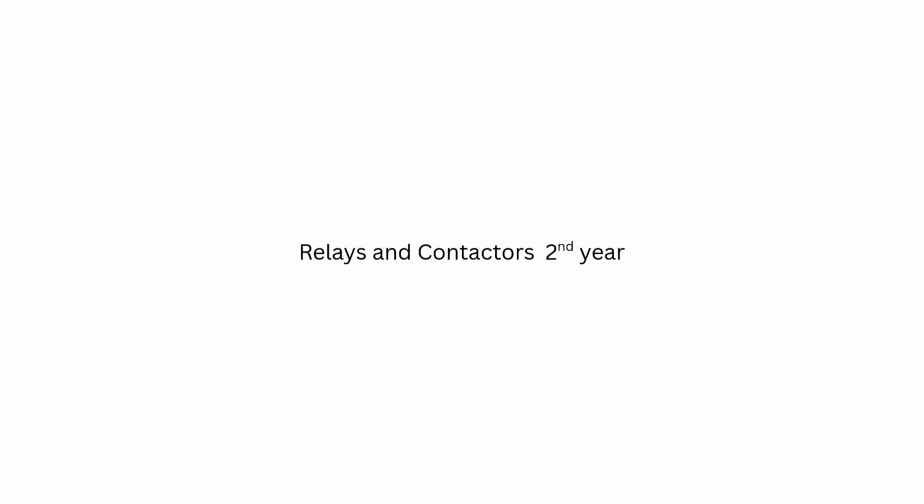Okay, so let's start simple. Let's say I'm just switching a small heater or a fractional horsepower motor. For that, you'd use a power relay. They're often open type, so you can see the contacts, and they're rated up to about 30 amps. And they're mechanically simple, but what's the catch? The catch is they are not designed for fast or frequent cycling. They're built to turn on and stay on for a while. Long, steady holds. Got it.